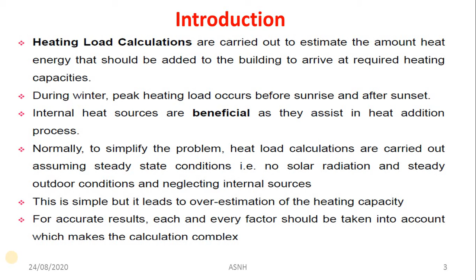So just take the example of one restaurant, or take the example of one commercial building. No doubt we must consider the static condition, and we must first focus on the design geometry of that building, like the orientation of that building, that is, the facing of the building, then sun radiation, the amount of heat radiation falling on the surface of the front side of the building. Also, we must consider the material of that building. So this is the most important step of heat load estimation.